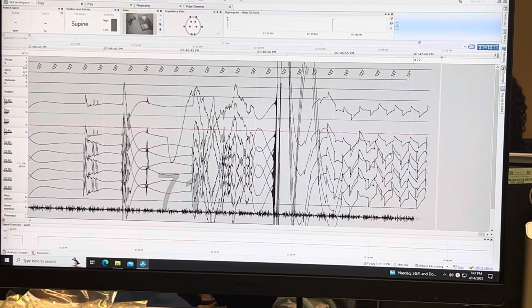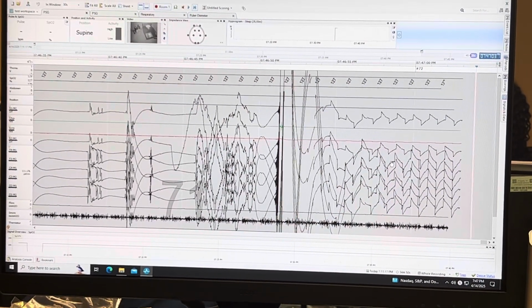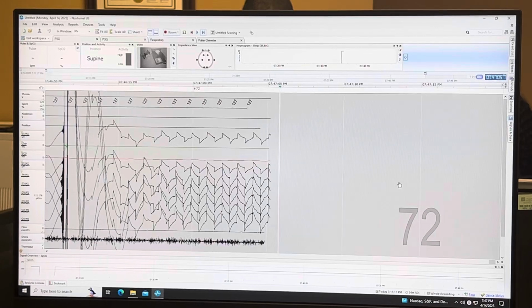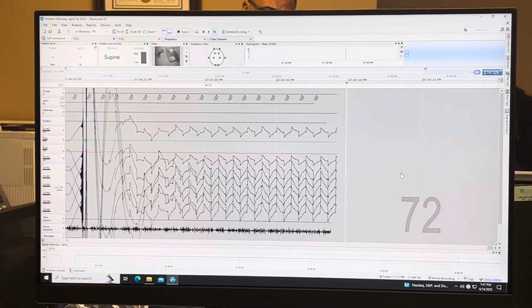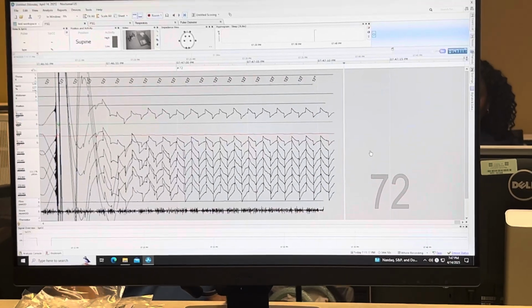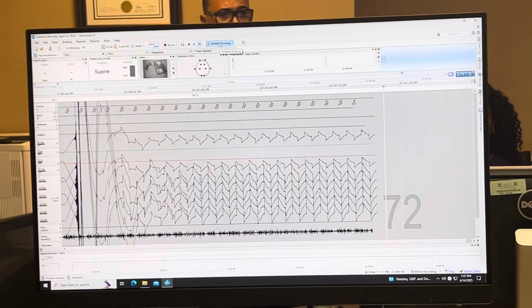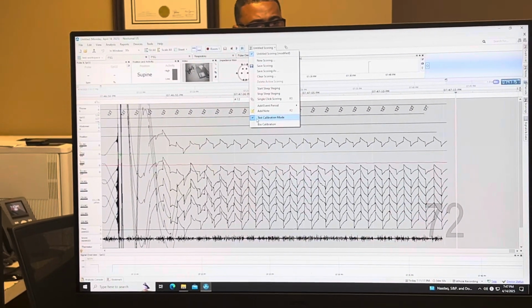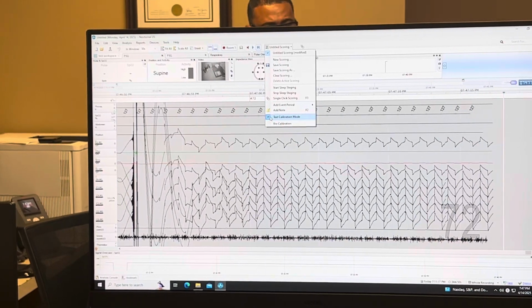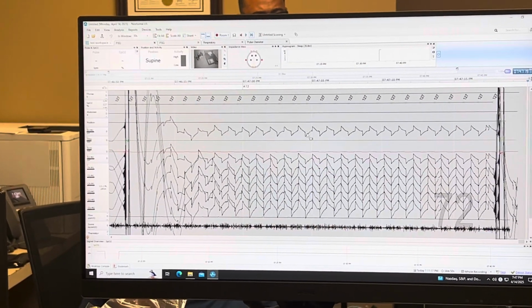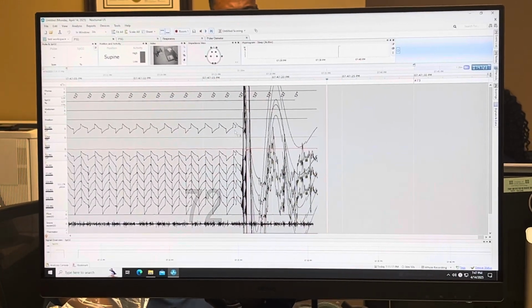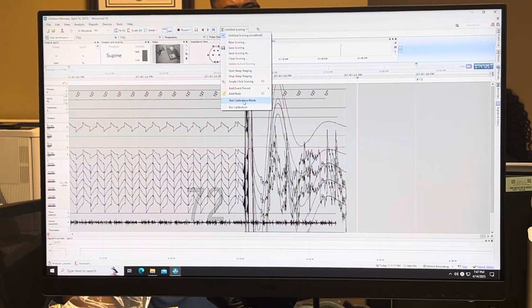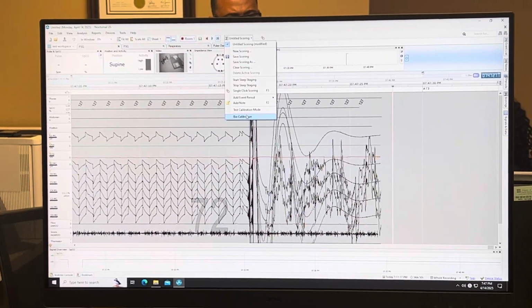The quirk here with the test cal or the cal stamp is it's going to run like that forever, unless you stop it. So you want to let it run for like an epoch, and then you can come back into untitled scoring and uncheck that test cal mode, and it'll stop doing your electrical cal. And the biocals are in there too, right? Yep, and then your next drop down is your bio cal.